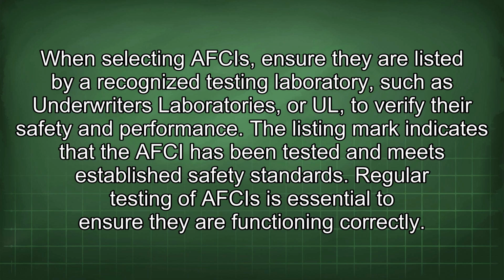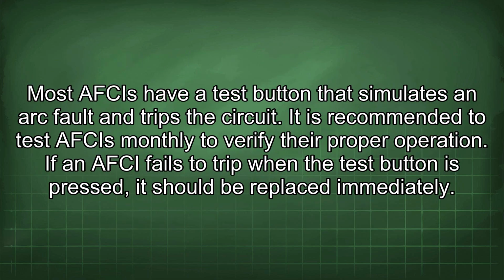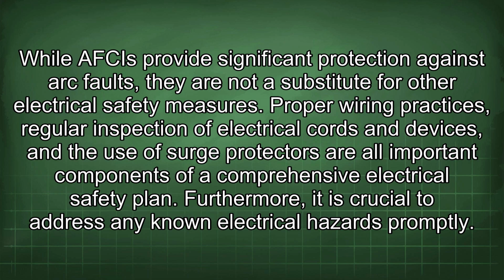Regular testing of AFCIs is essential to ensure they are functioning correctly. Most AFCIs have a test button that simulates an arc fault and trips the circuit. It is recommended to test AFCIs monthly to verify their proper operation. If an AFCI fails to trip when the test button is pressed, it should be replaced immediately. While AFCIs provide significant protection against arc faults, they are not a substitute for other electrical safety measures. Proper wiring practices, regular inspection of electrical cords and devices, and the use of surge protectors are all important components of a comprehensive electrical safety plan.